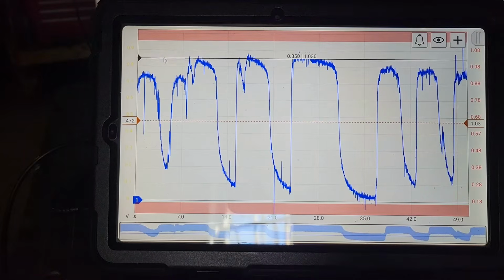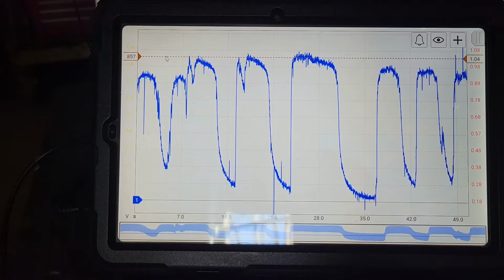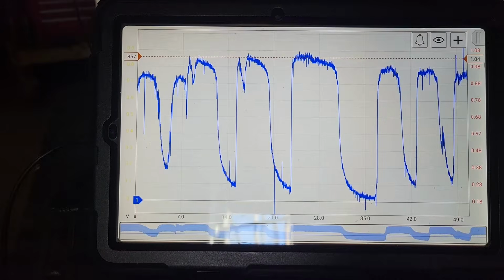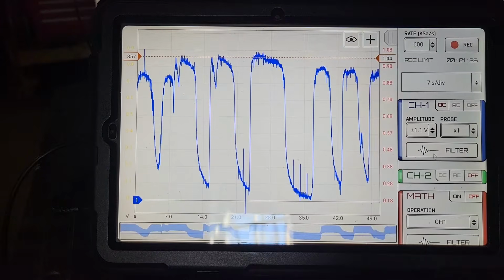Like this bit of static here, where would you put it? You'd basically just go for the middle. We're like 857 there. But what you could do is go to that channel and go to the filter. Now I kept the cursor here so we know if we lose amplitude, it's going to drop down and look like one of these. On some voltages it does. I'm not sure the exact reason, but if I want to clean it up, that's my rule. If it drops in amplitude, it's not going to do you any good, because you're sacrificing a clean waveform for actual measurement, because your cursors aren't going to be where the signal actually was.